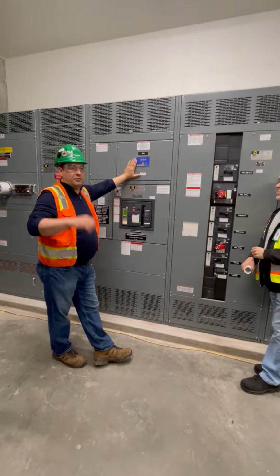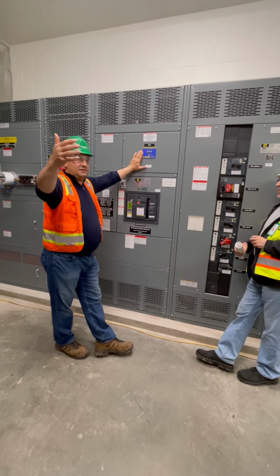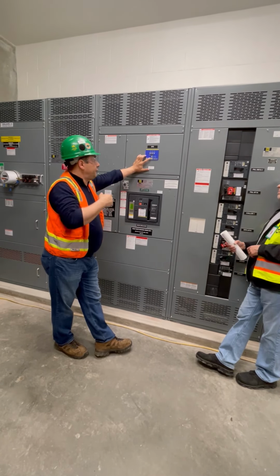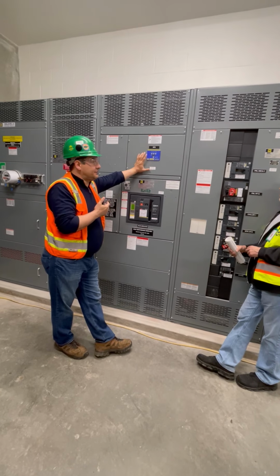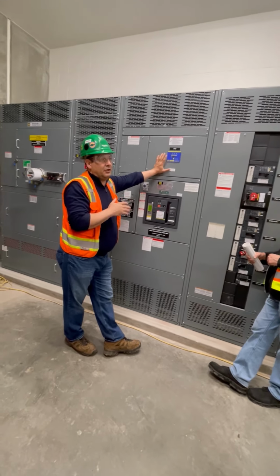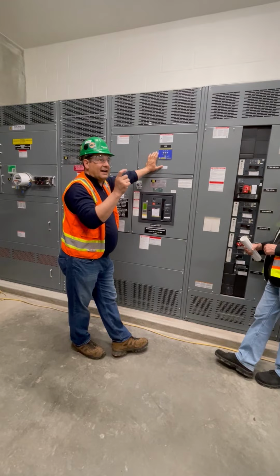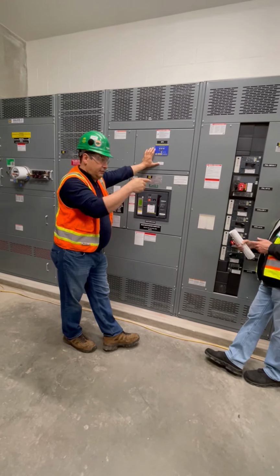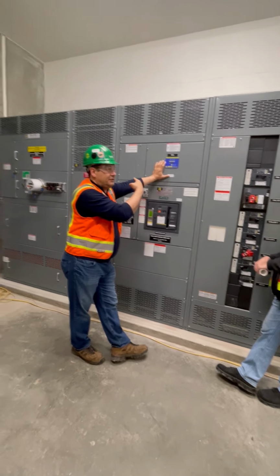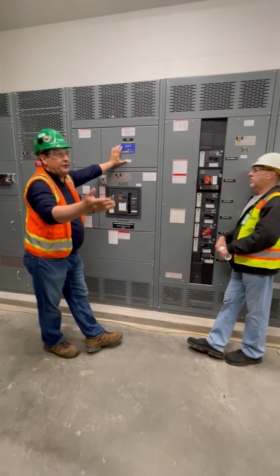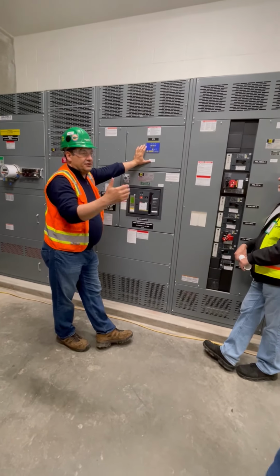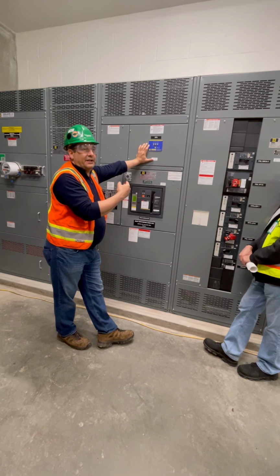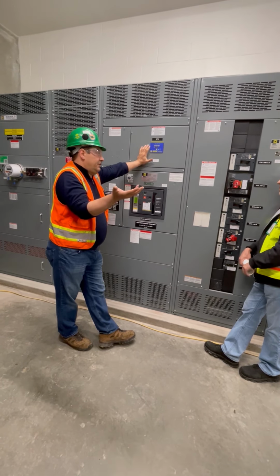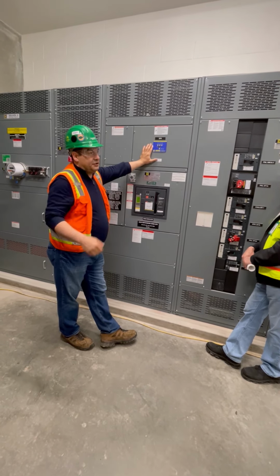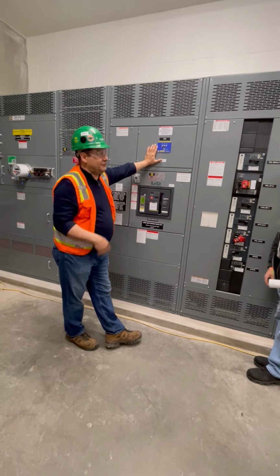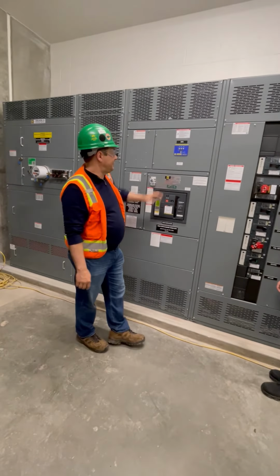If you want to take this to your building management system, you can for the alarm, and it gives you some status, right? But it's really basic. It doesn't give you a whole lot, but it does have an alarm on it. It has a contact that gives you an alarm. If one of the phases takes a hit and goes out, you get that alarm if you want to go in that direction. It will save you from coming in here every couple of months to look at it, right? Because you're already monitoring it. But you either have that or, like I said, it's a good idea to come in here every so often and check those just to make sure it's still protected.